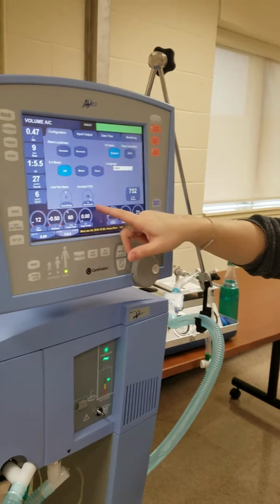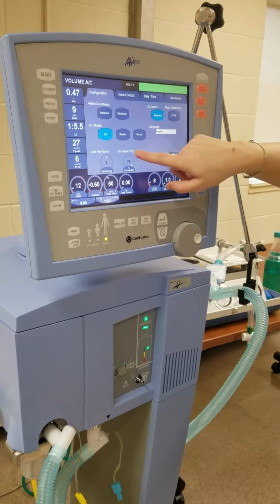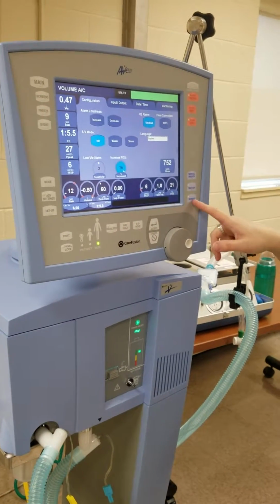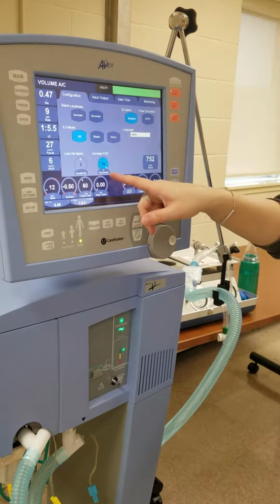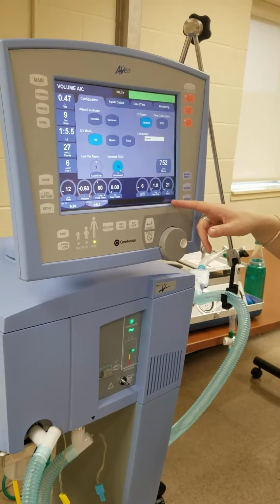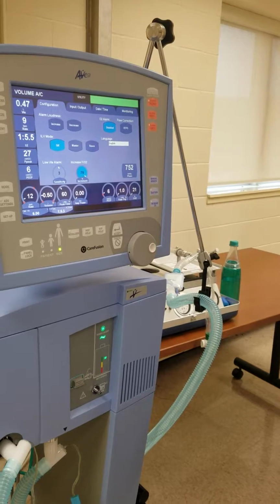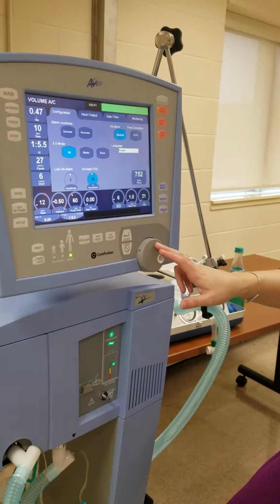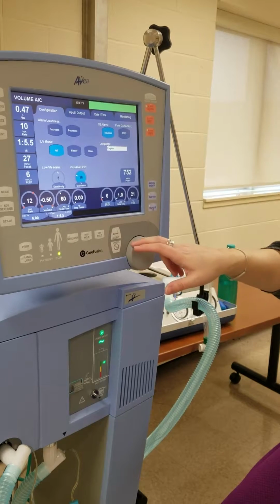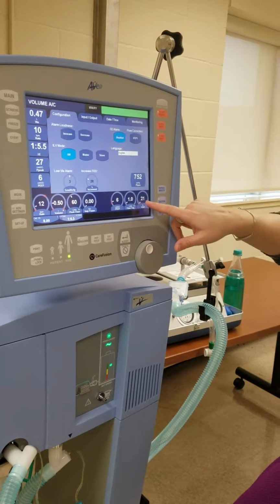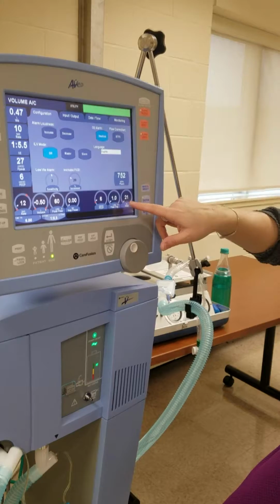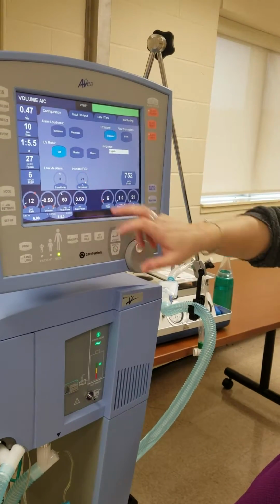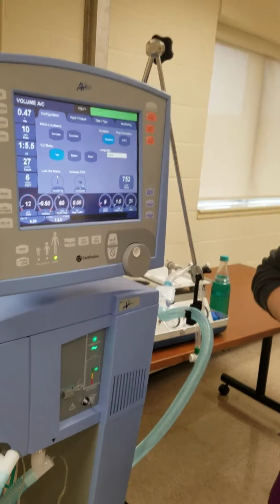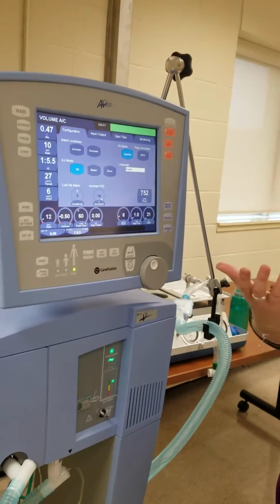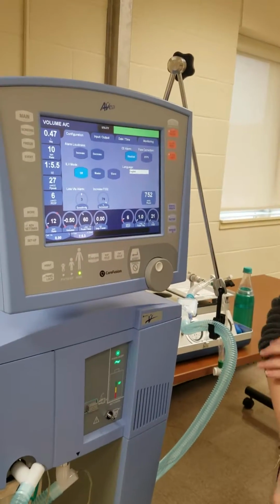The one time I did use this screen a lot in pediatrics, we actually would change that increase FiO2 button. This tells the machine what to do when we hit this button. So right now it's at 79, meaning if we're down even as low as 21%, we always hit 100% as soon as we hit that button. Let's say we only want to go up by 20% when we hit that button. We'd adjust that there, and now every time I hit this button, it's only going to go up 20 points from where it was before. In adult land, it's pretty rare that you have a patient that you don't want to have 100%. In pediatrics, it's pretty often that you have patients you don't want 100%. The rest of that's all like internal computer kind of stuff.